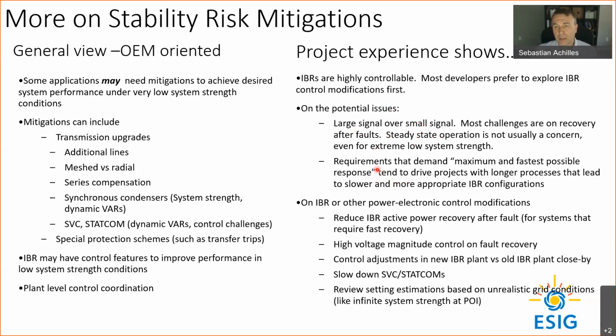Another issue that is not too uncommon is when there are requirements of having maximum and fastest possible response time. So very aggressive controls or very fast control requirements in weak grids, those two don't go together. So very often, after a long process of studies, there is a conclusion that some of the controls need to be slower for weak grids, despite the fact that maybe the requirements ask for very fast response in a standard application.